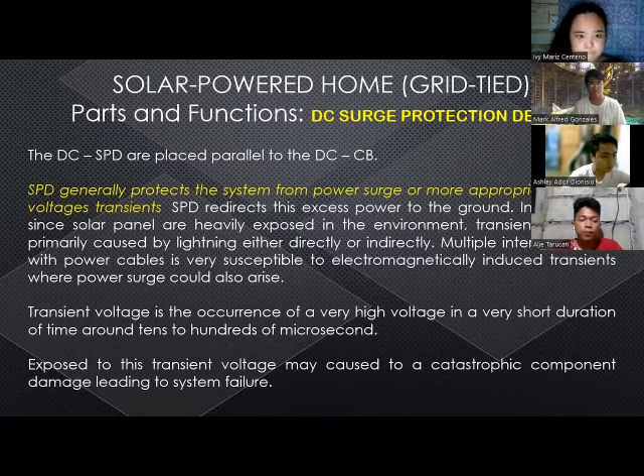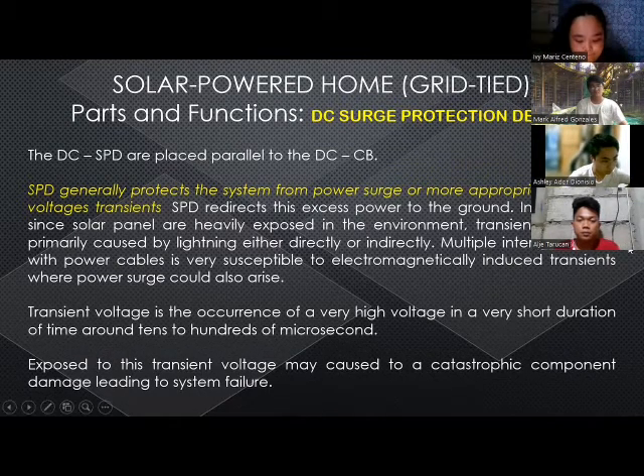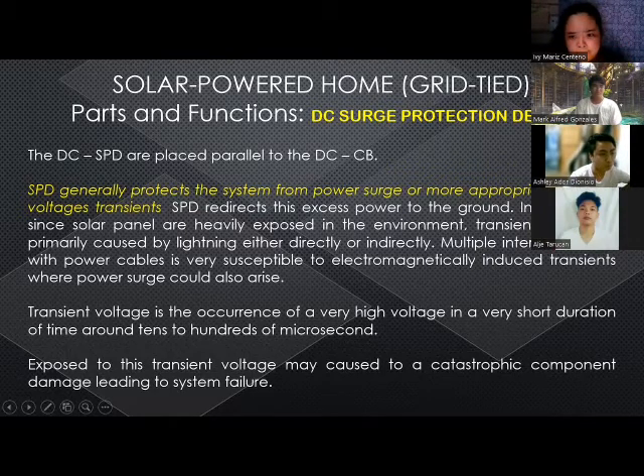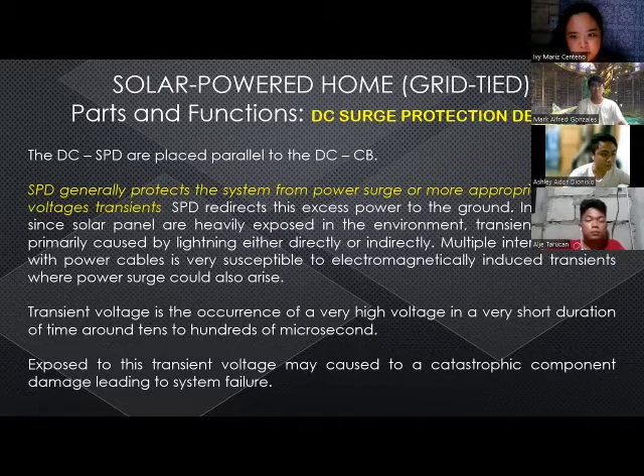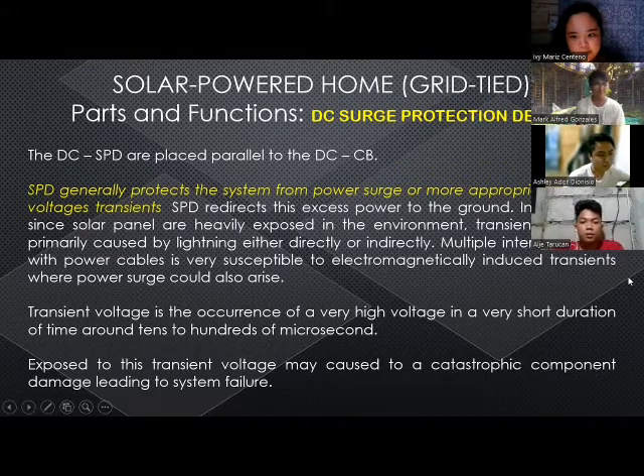So, transient voltage is the occurrence of a very high voltage in a very short duration of time, around 10 to 100 microseconds. That is how fast that power surge is. Exposure to this transient voltage may cause catastrophic component damage, leading to system failure. It can damage our systems because of the catastrophe. If we have no DC surge protection, our system may possibly be damaged. That is why we install this, to prevent the sudden rise in voltage due to lightning.